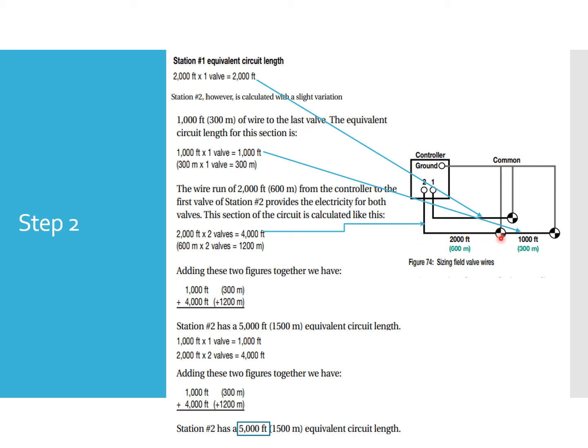Now remember, like we worked on sizing pipe last week, this is a similar situation where if both of these valves are operating at the same time, it's carrying the load of both of these valves. Well, this valve is 2,000 feet away. This valve is actually 3,000 feet away. So we need to add all of those together. So we have 2 of these valves that go 2,000, plus we have this other additional 1,000, which comes out to 5,000 feet of equivalent circuit length, because we have 2,000 of that plus 2,000 plus 1,000.